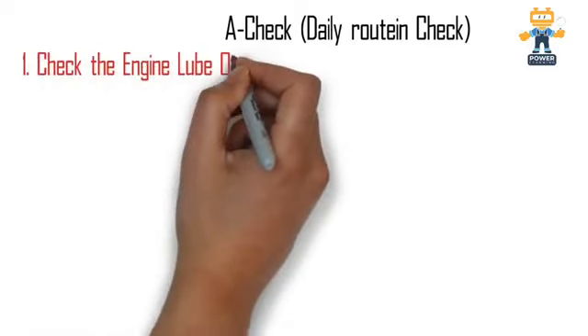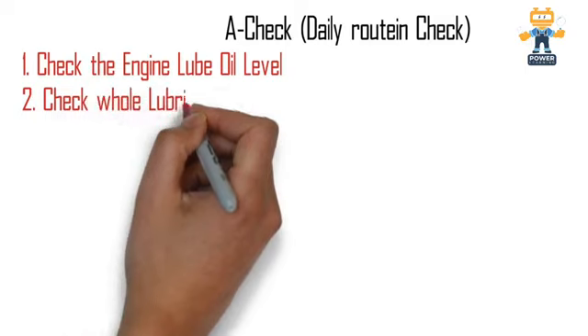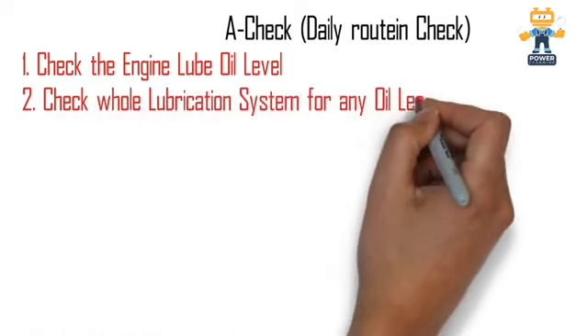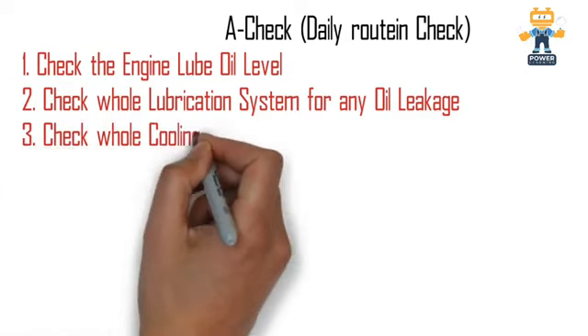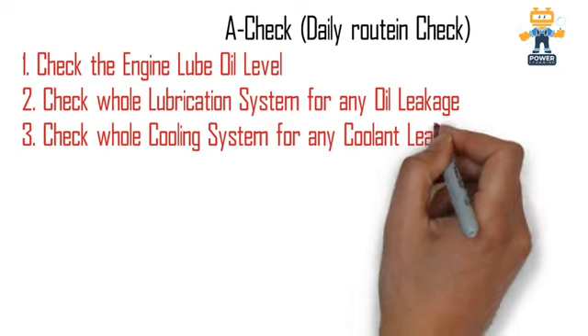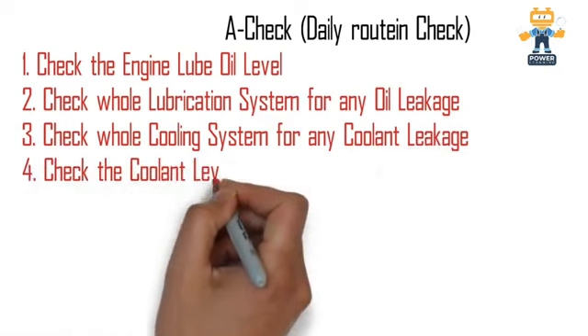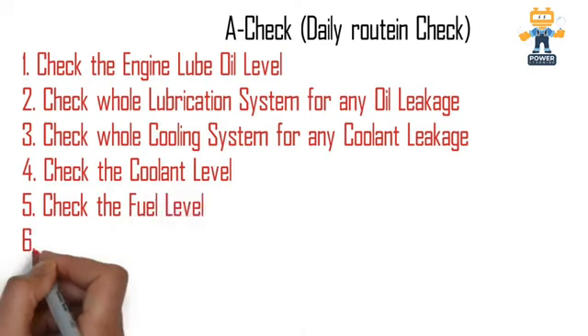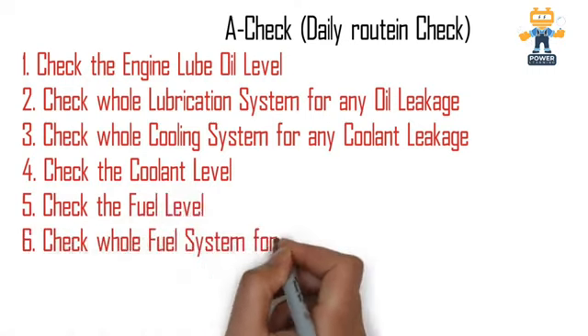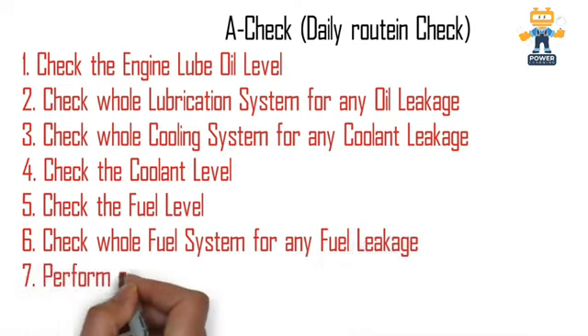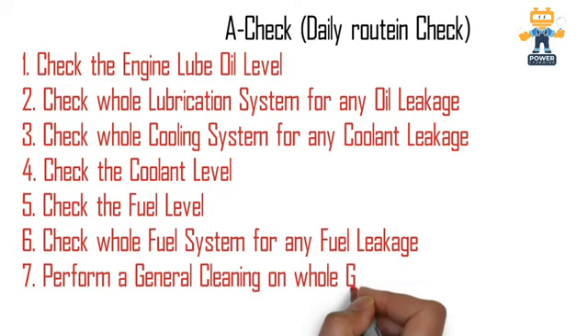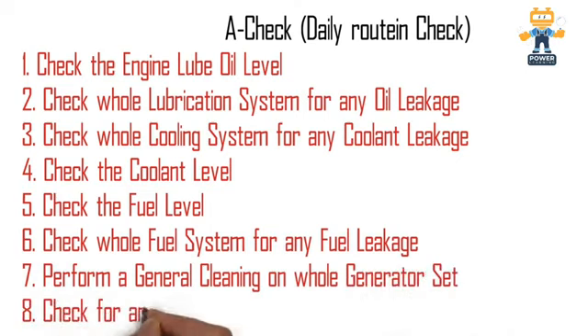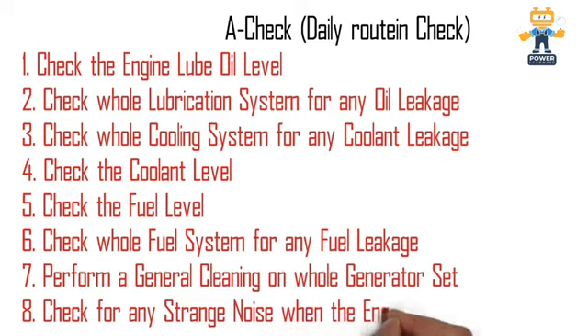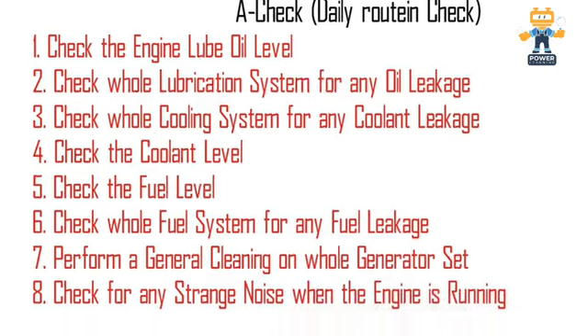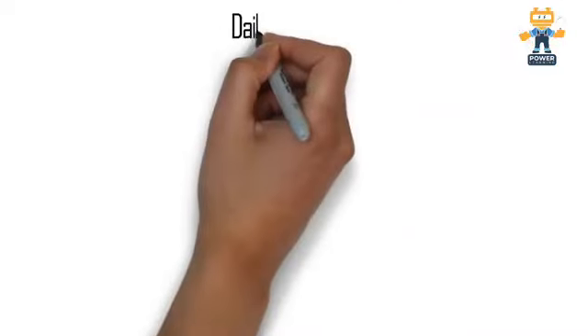Number 1 is the daily routine checks. In the daily routine we have to check the engine lube oil level before starting the engine, and check the whole lubrication system for any oil leakages. Number 3 is to check the whole cooling system for any coolant leakage and the radiator water level, and check the coolant level in the radiator also. Check the fuel level in the diesel tank and check the whole fuel system for any fuel leakages. Also perform a general cleaning of the whole generator on a daily basis. Check for any strange noise when the engine is running. So these are the daily routine checks, and you have to do them on a daily basis.